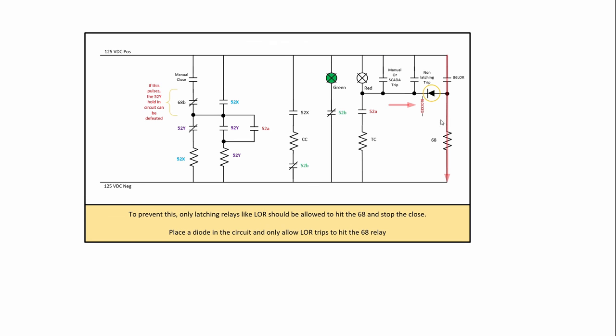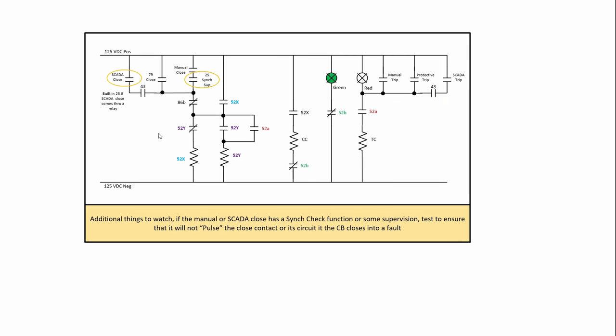So to protect against that, you have to make sure that the 68 is only picked up from latching relays like lockouts and any non-latching like your manual trips or any protective trips that are like from a relay will need to be blocked through a diode and because if you don't do that, that could be pulsed and it could defeat the anti-pump logic.